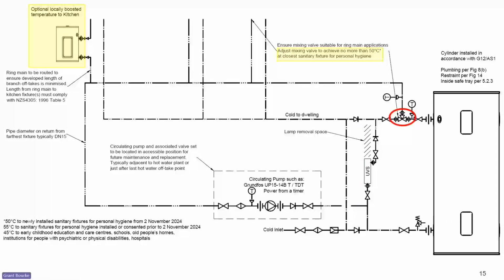This bit's kind of important, and I'll explain on the next slide how this works, but this is a leg that bypasses the cylinder on the ring main return and joins in with the cold before the mixing valve. I've been to lots of particularly smaller domestic installations with plumbers that have had a bit of a crack at a ring main that this is entirely missing. If this is entirely missing, the system won't work properly, water won't circulate properly, and I'll explain on the next slide why that is. And yeah, you'll stuff the pump and you'll stuff the mixing valve over time.